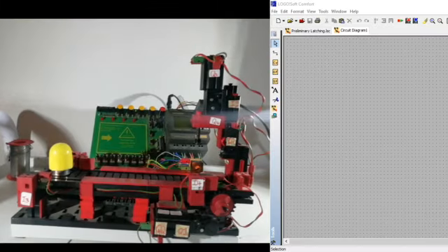The most important thing when it comes to testing is that you need to know whether your inputs are currently switched on or off. My aim now is to identify the nature of my inputs, whether they are normally closed or normally open.